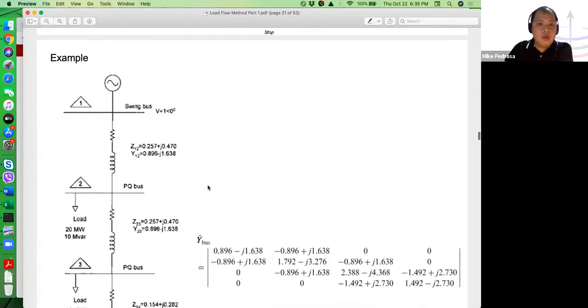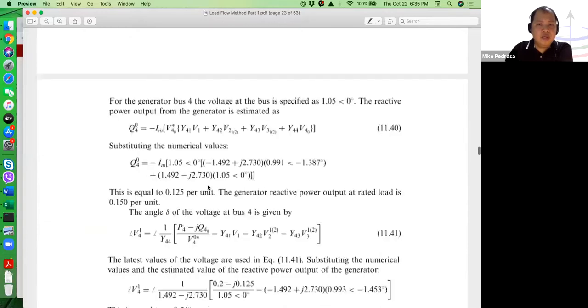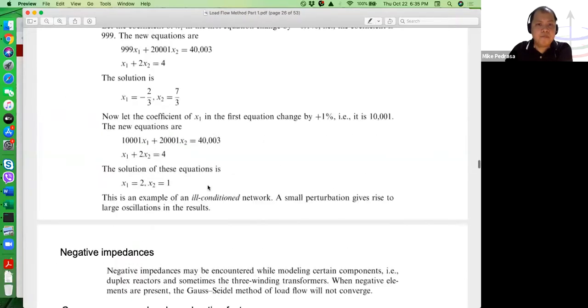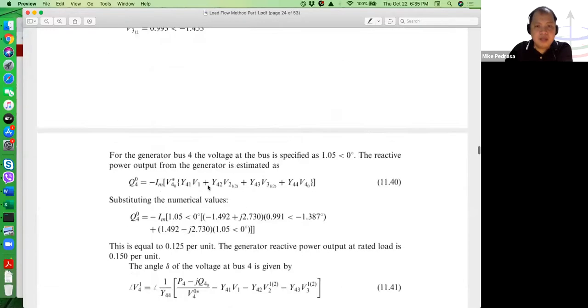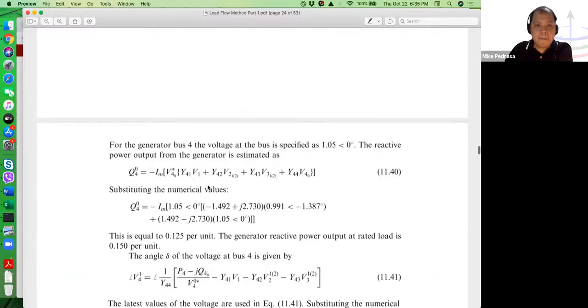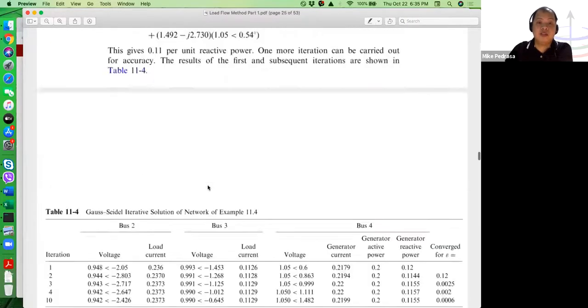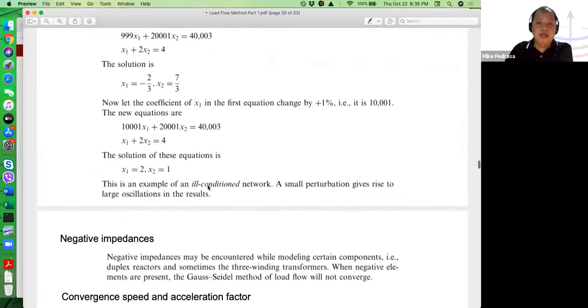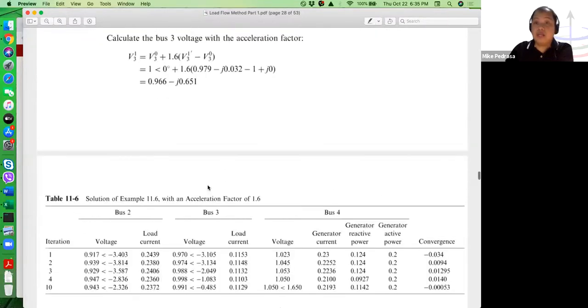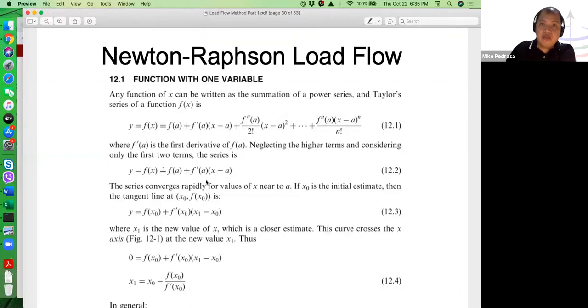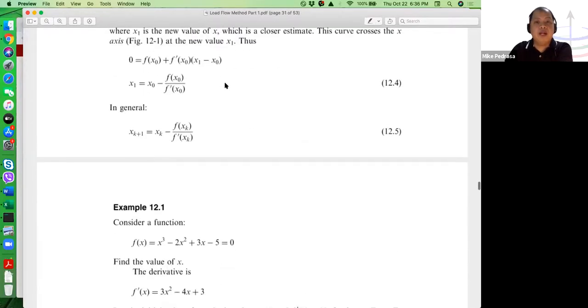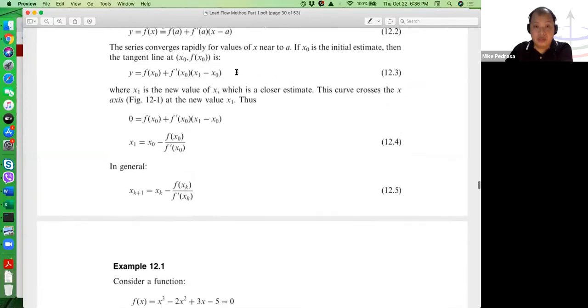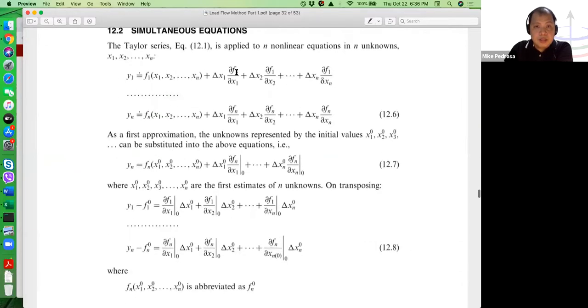To summarize the Gauss-Seidel formulation: use the basic voltage equation for load buses; for generator buses, estimate Q, check limits, and if within limits solve only for the angle. If Q exceeds limits, use Q_max or Q_min and treat the generator bus as a load bus.